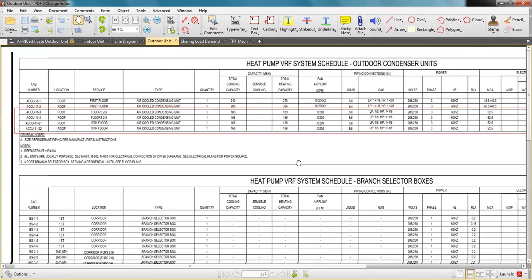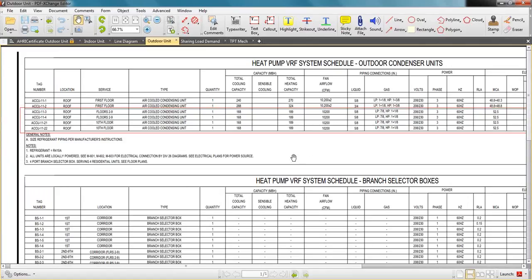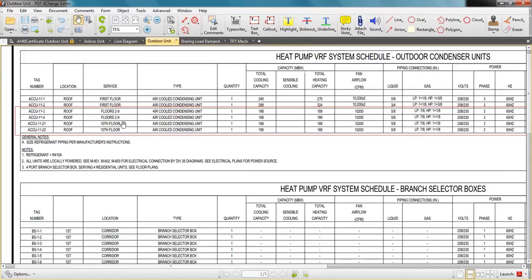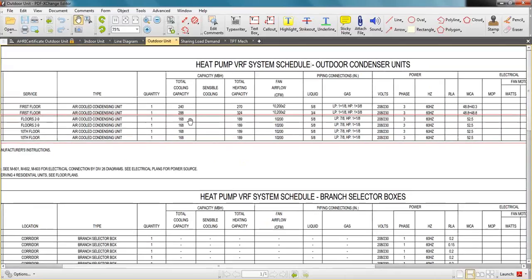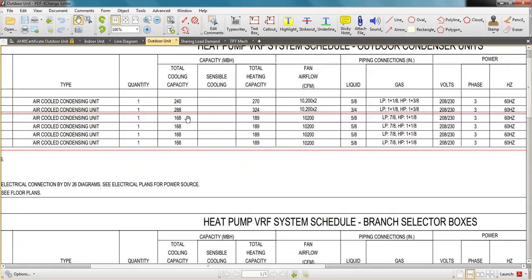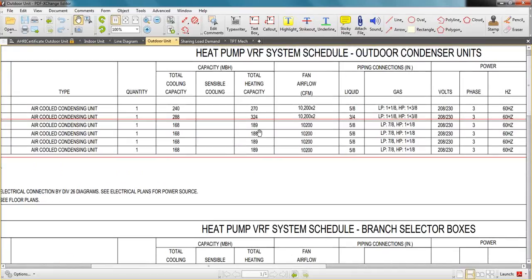I wanted to show you a schedule that I have for a property that was utilizing heat pumps and a VRF. This is a multifamily project, 10 stories, going through an upgrade and changing out to a VRF system. Basically, floors 2 through 9 and the 10th floor get a total of 4 condensing units serving all those indoor units. It's an air-cooled condensing unit with quite a large cooling capacity, 168 MBH, and 189 MBH when heating. That's a larger outdoor unit paired up to multiple indoor units, splitting up the cooling capacity demand based on how many units it's connected to.